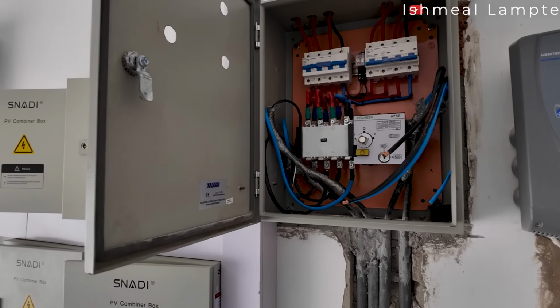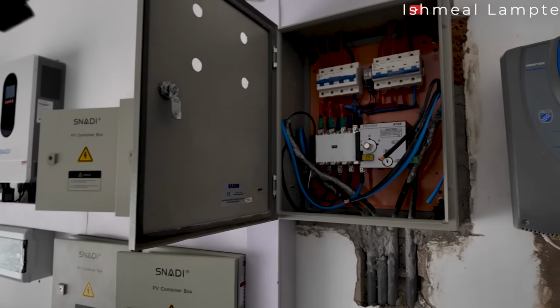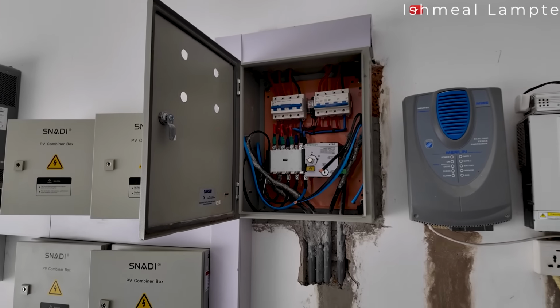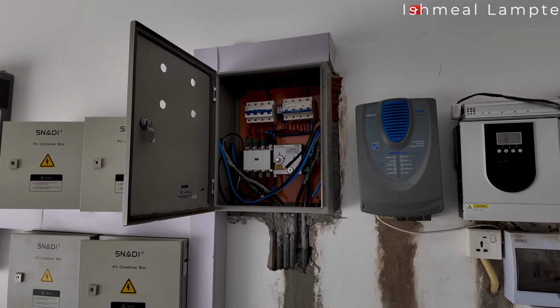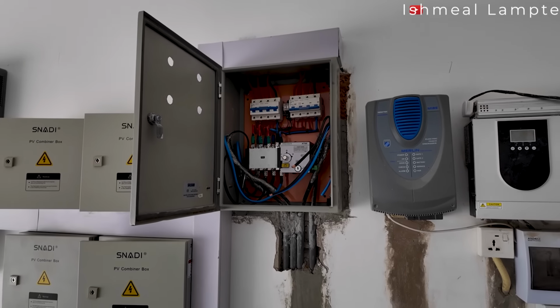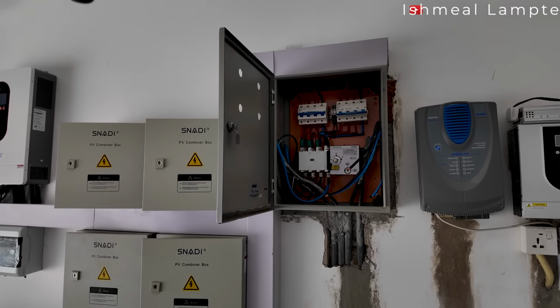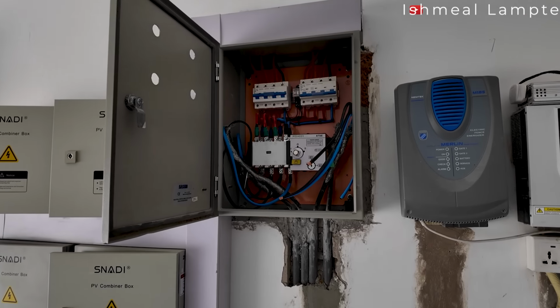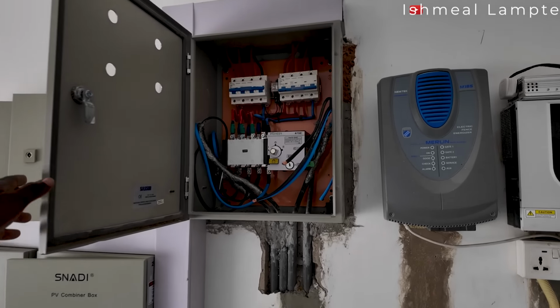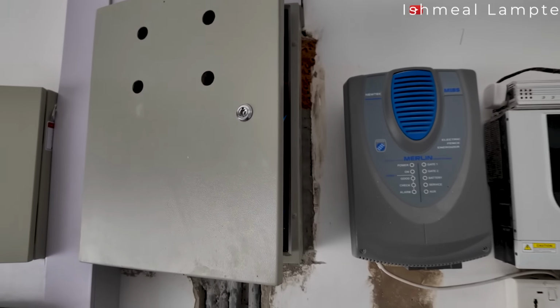This is taking the power coming from the panels and sending it into the other ATS, which is configured with a generator cable. In case there's supposed to be a generator, that will go into that ATS, yes, before it goes into the distribution board.